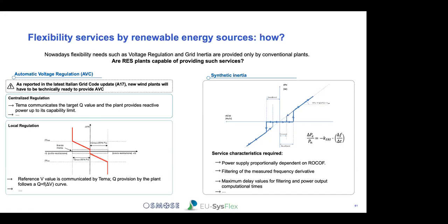So as far as voltage regulation is concerned, what we basically want to ask of these plants is to be capable of varying their reactive power provision according either to a Q set point or to a reference voltage set point, for what is called centralized or local regulation.